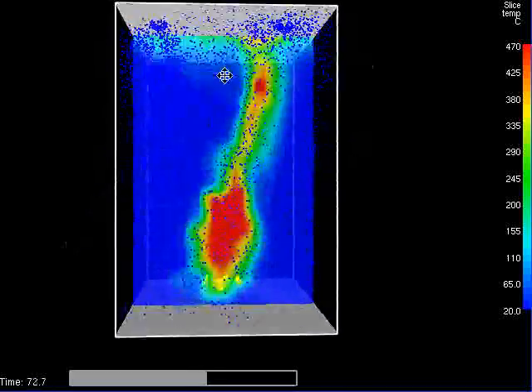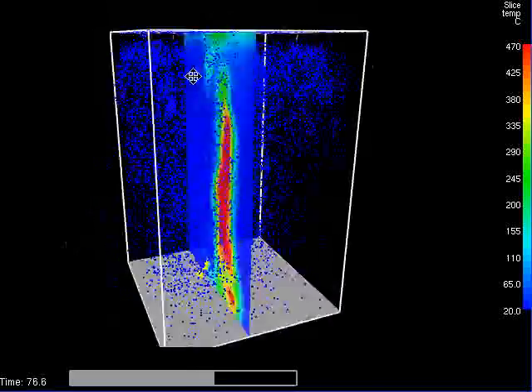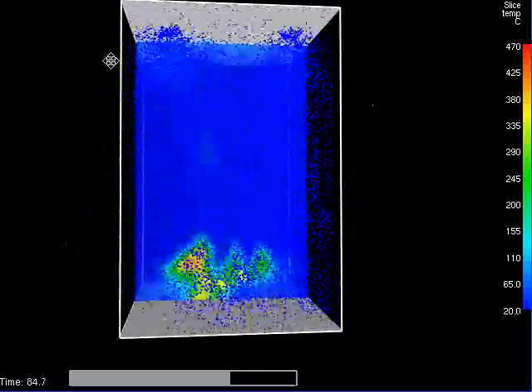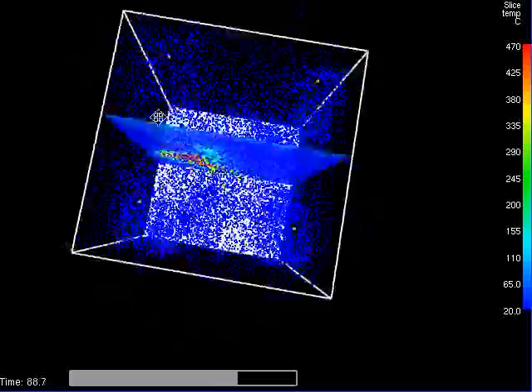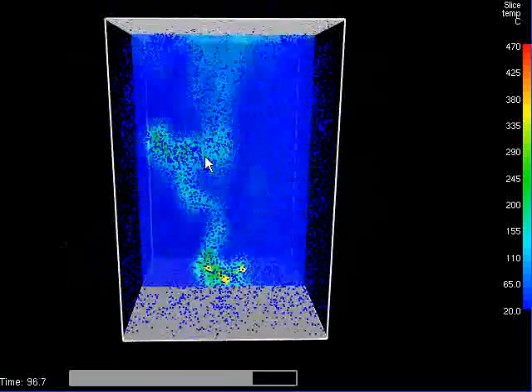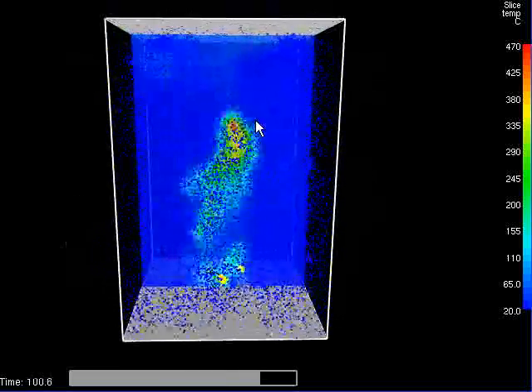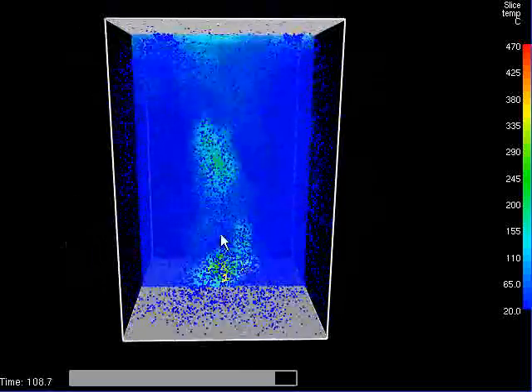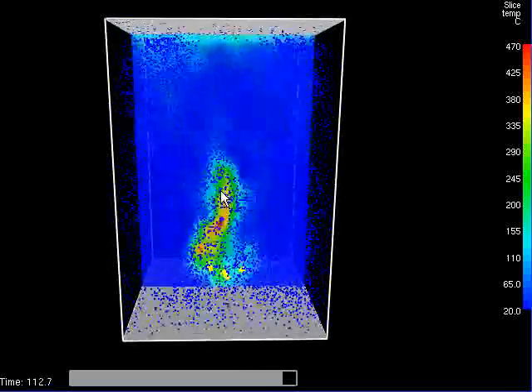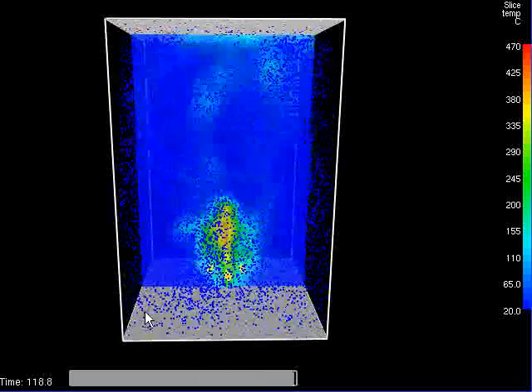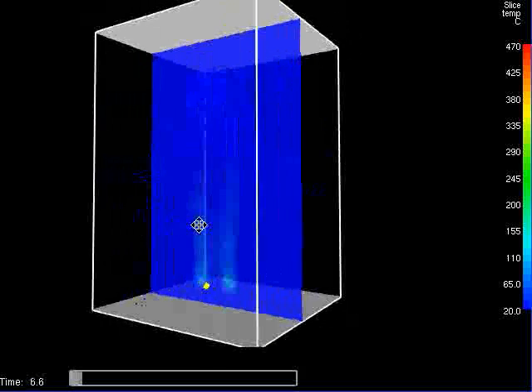Not long after that, the third and the fourth sprinkler also goes off. The temperatures still continue to rise, and all four sprinklers are now going off. You can see the result is that the fire plumes — the temperatures and the gas phase temperatures — are significantly suppressed. Then we reach the end of the full simulation and it just starts all over again.